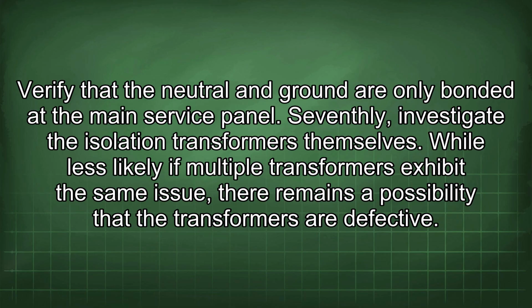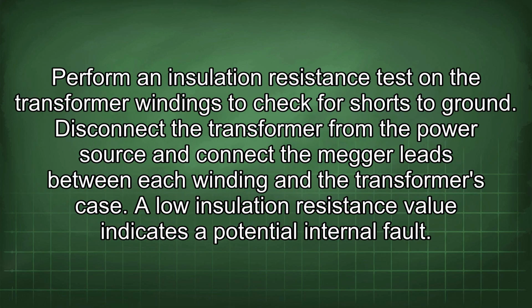Seventhly, investigate the isolation transformers themselves. While less likely if multiple transformers exhibit the same issue, there remains a possibility that the transformers are defective. Perform an insulation resistance test on the transformer windings to check for shorts to ground. Disconnect the transformer from the power source and connect the megger leads between each winding and the transformer's case. A low insulation resistance value indicates a potential internal fault.